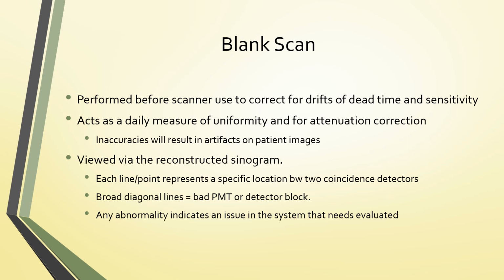If you see broad diagonal lines on a blank scan, it means there's a bad PM tube or a bad detector block. If it's a bad PM tube, it tends to be a thinner line, and if it's a detector block, it tends to be a thicker line. Remember, with the scanner design, you have several PM tubes coupled together in one detector block. So it makes sense that if it's just a bad PM tube, it would be a thin line, whereas a detector block is going to involve several PM tubes, so it's going to be a much thicker line that you will see. And any abnormality there indicates that there's an issue in the system that needs to be evaluated.